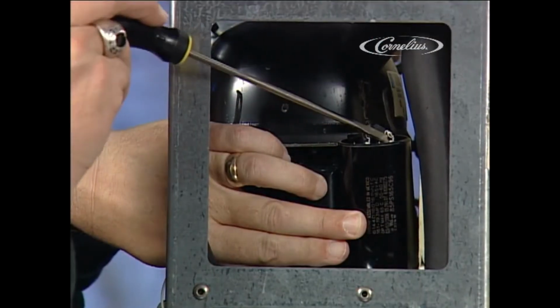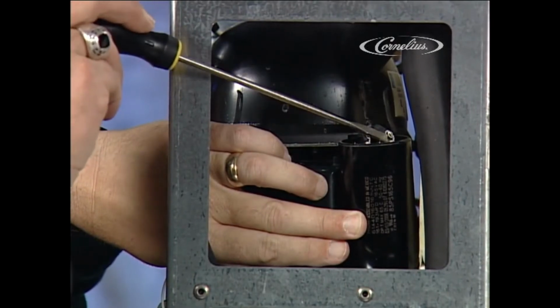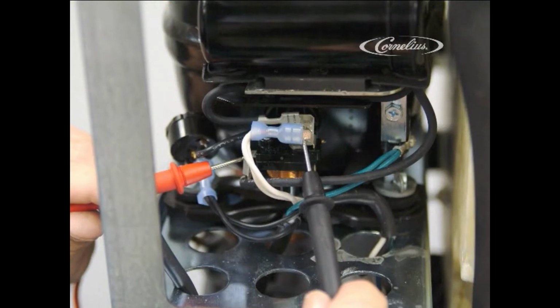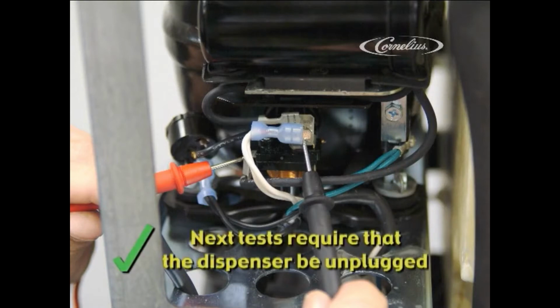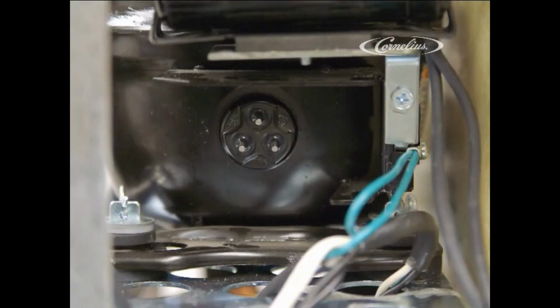If the compressor is silent, check to see the line voltage is indeed reaching the compressor. You do this by placing your volt-ohm meter probe on the overload lead and the neutral lead on the relay itself. If no voltage is present, check for loose or damaged wire connectors. The next tests require that the dispenser be unplugged. After you have discharged the capacitor as we stated above, remove the overload and relay from the compressor. The relay is removed by pulling straight back.